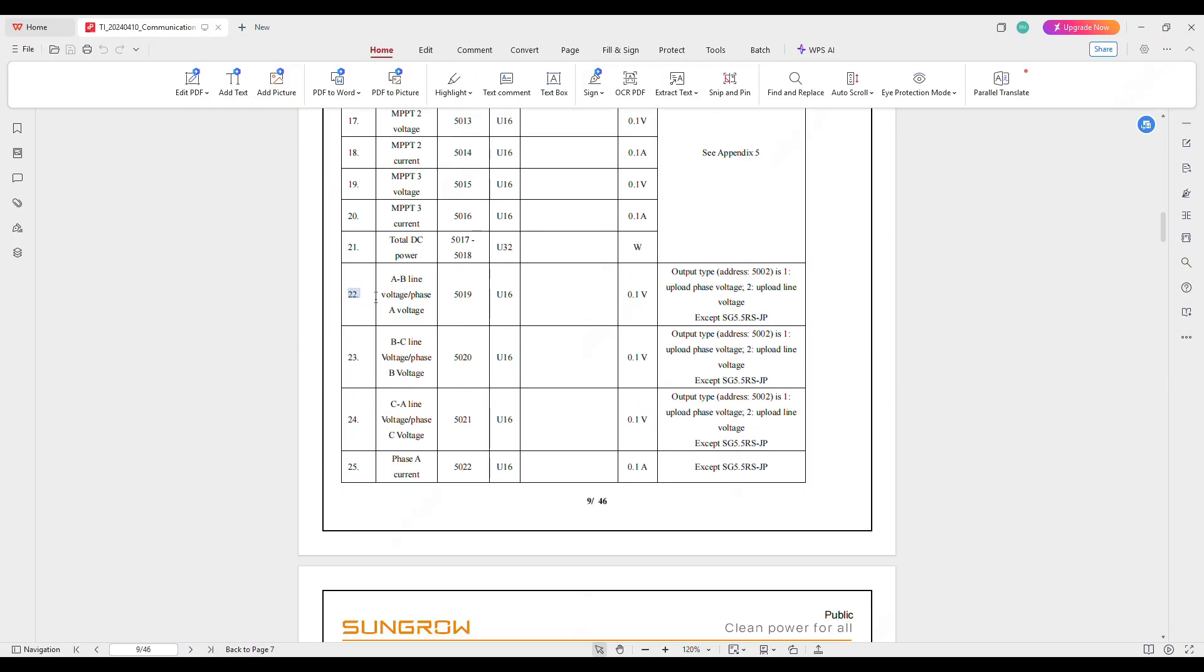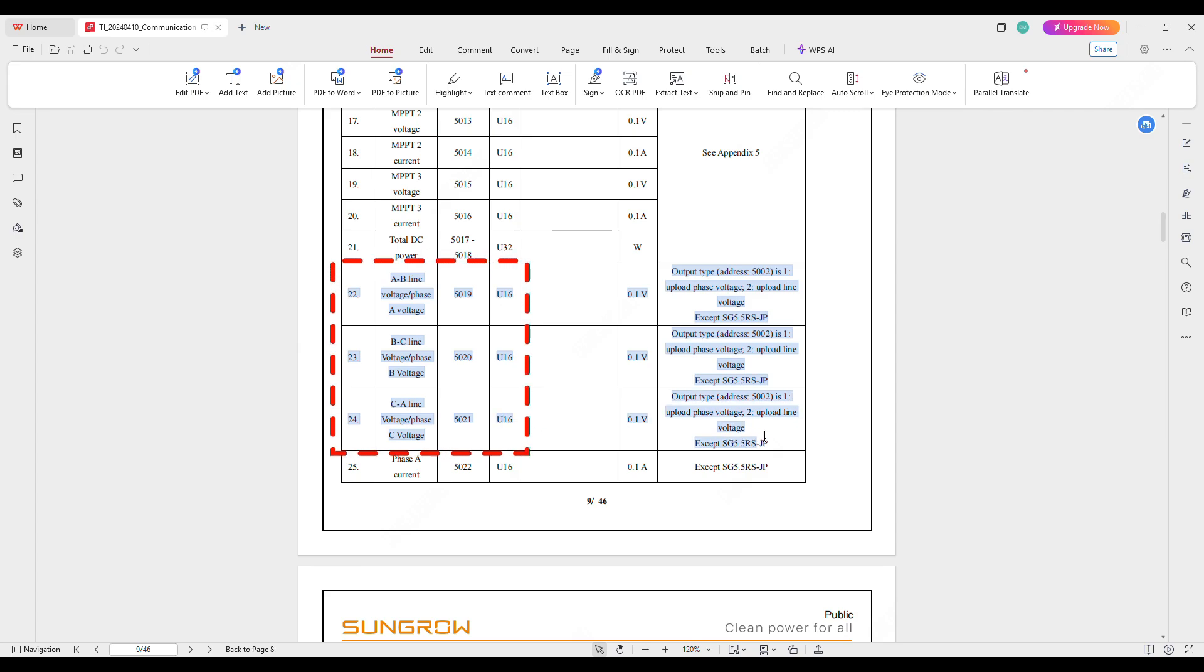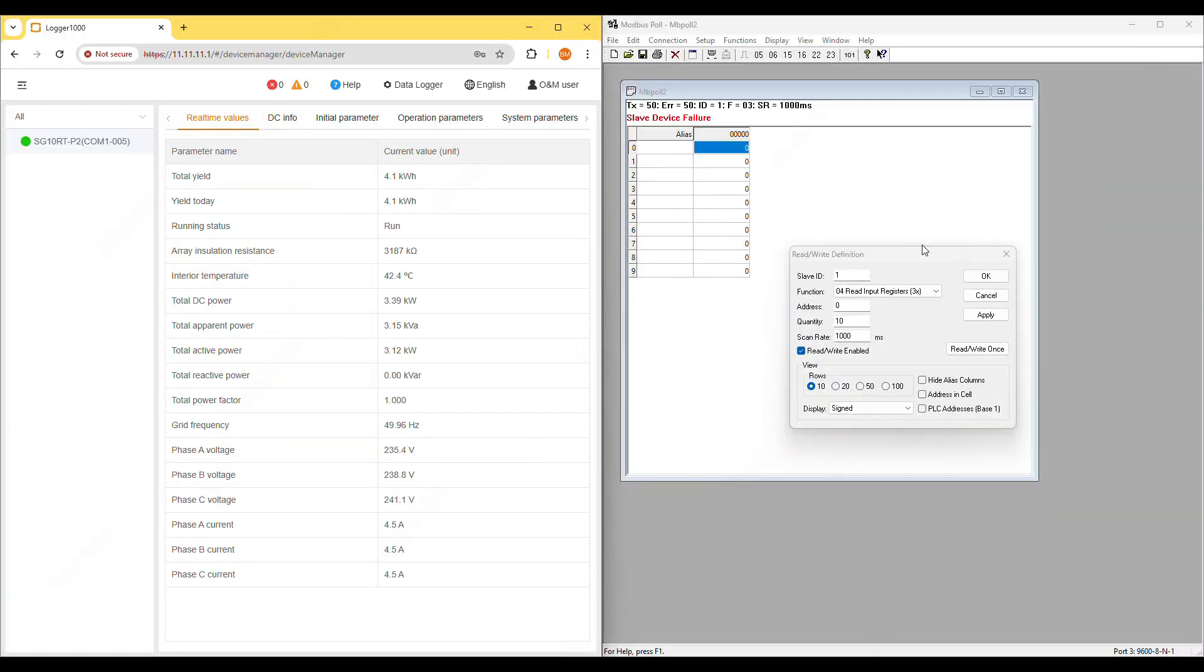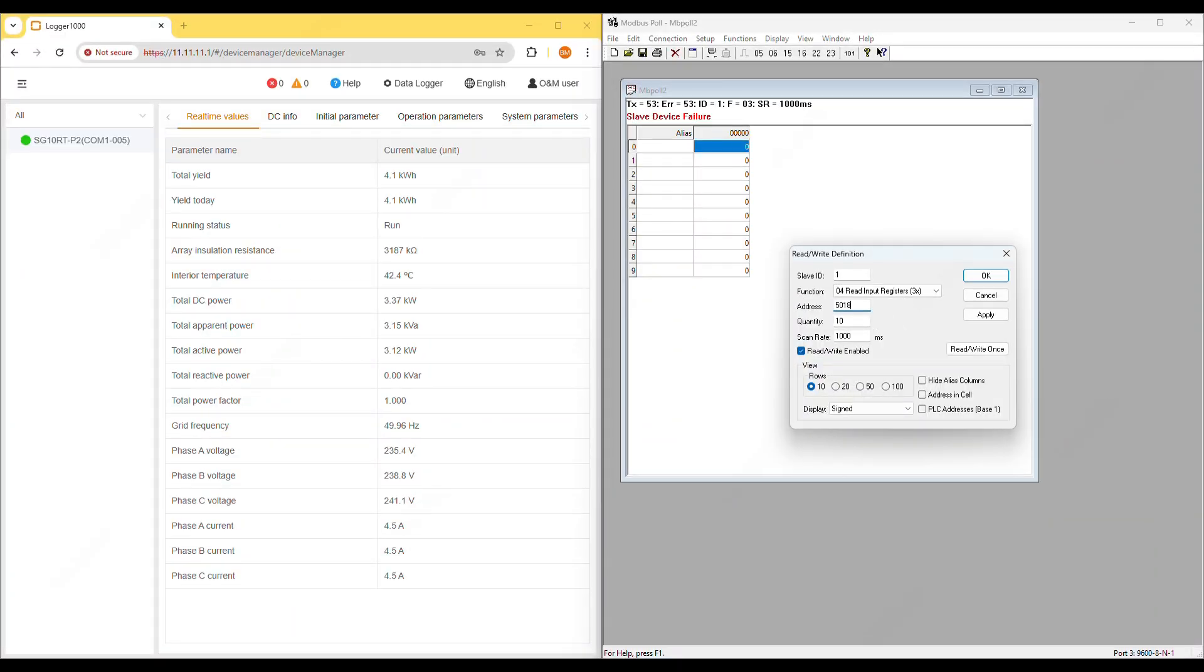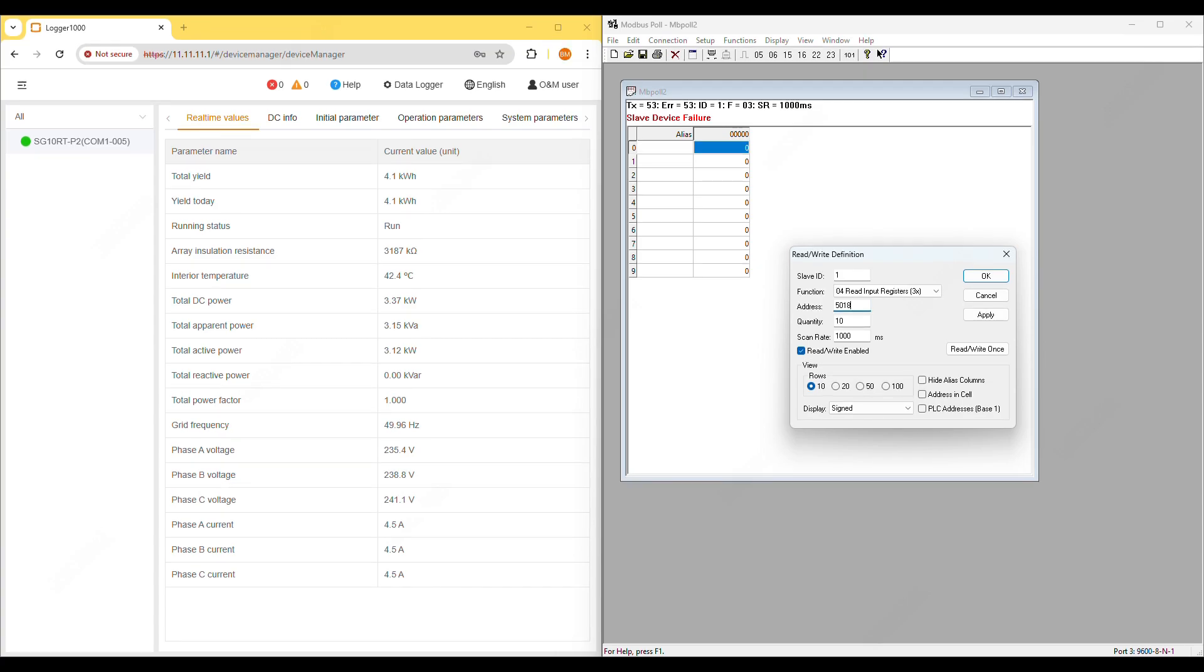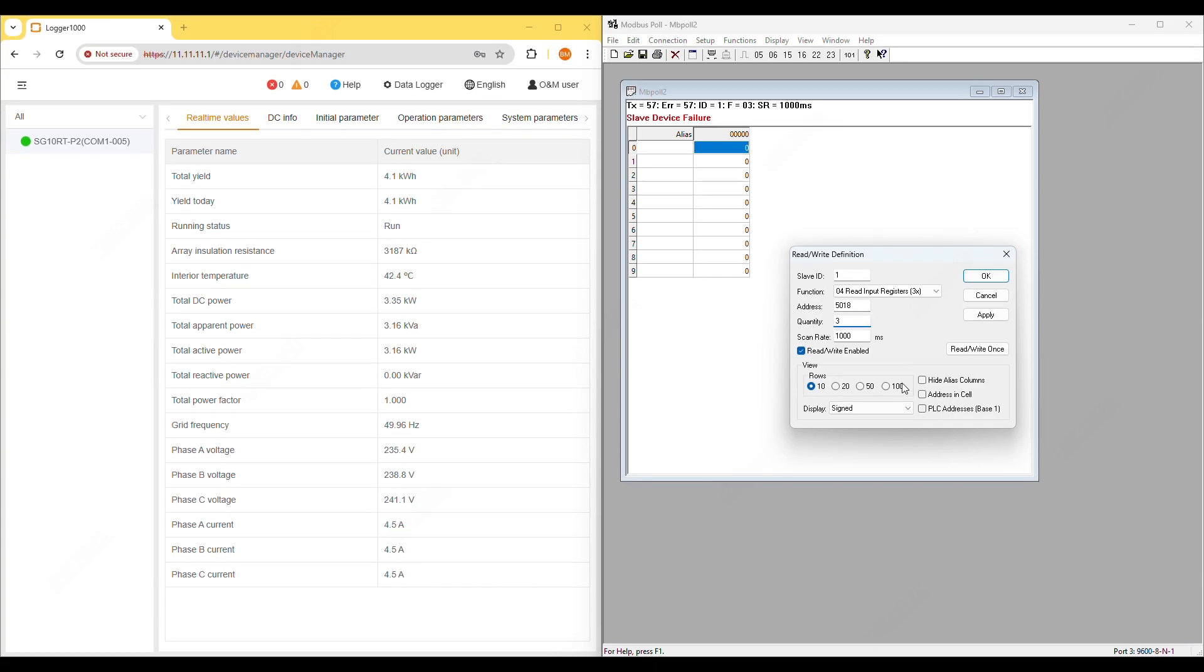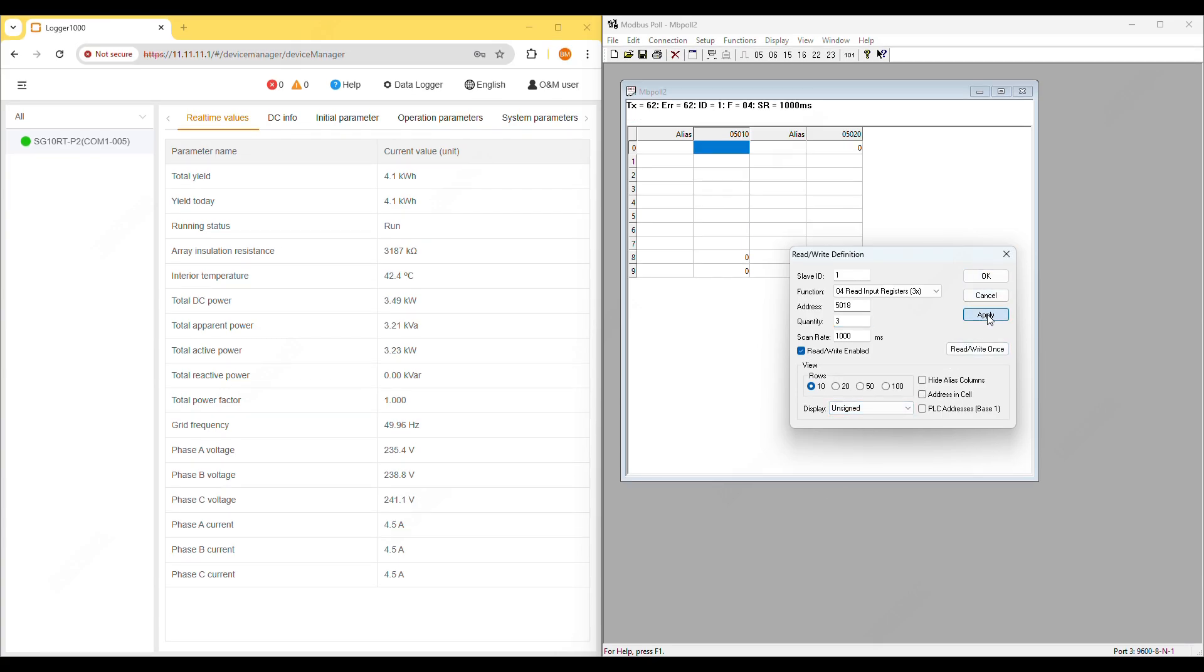Now let's check the register addresses for phase A, B and C voltages from the Modbus protocol document. The register address for phase A voltage is 5019. In Modbus poll you need to subtract 1 so enter 5018. Set the quantity to 3 so we can read phase A, B and C at the same time. Set data type to U16 and display to unsigned. Then click apply.